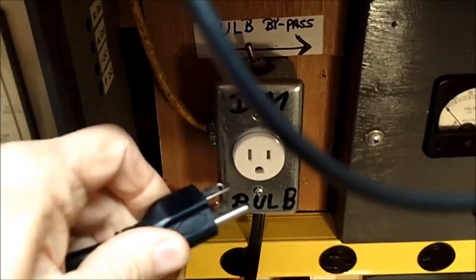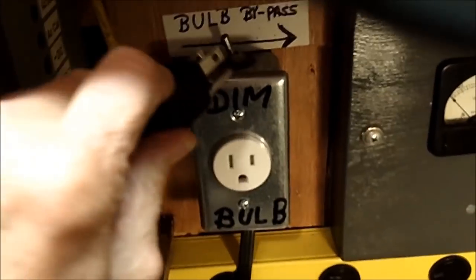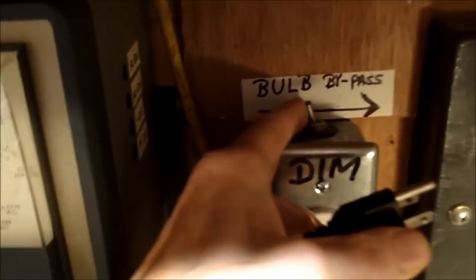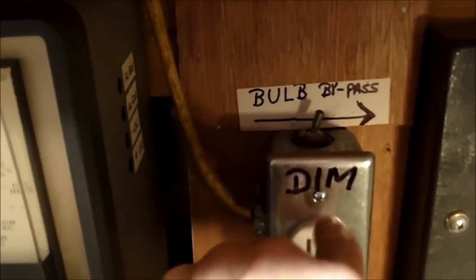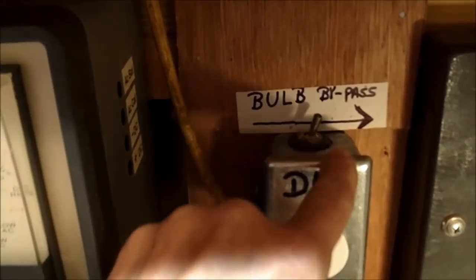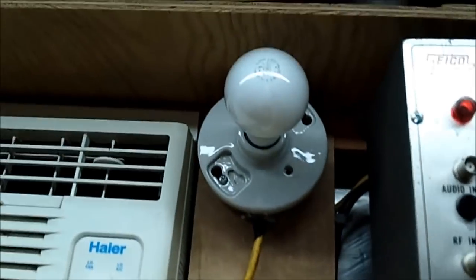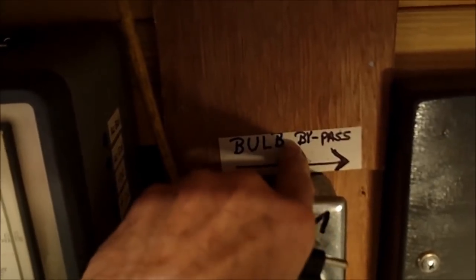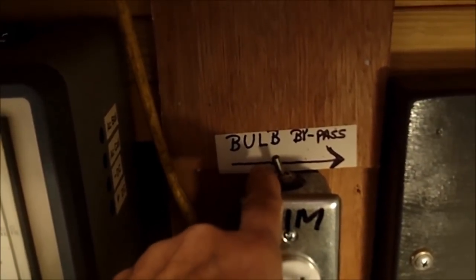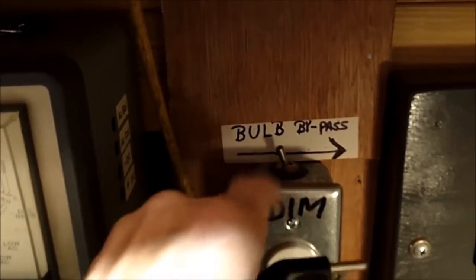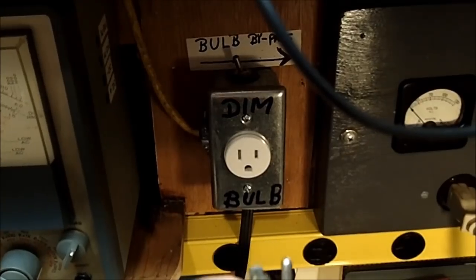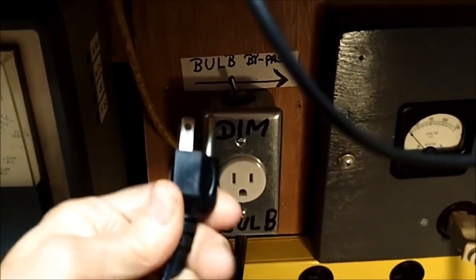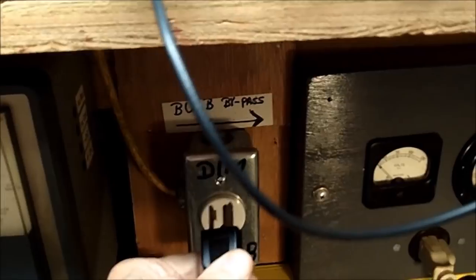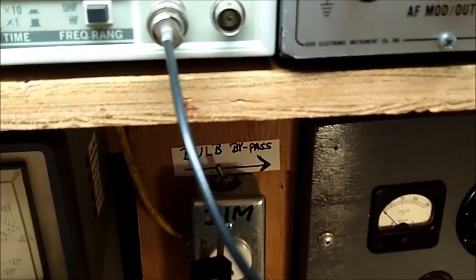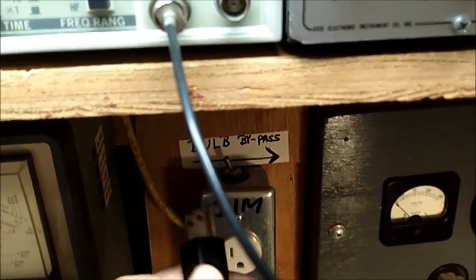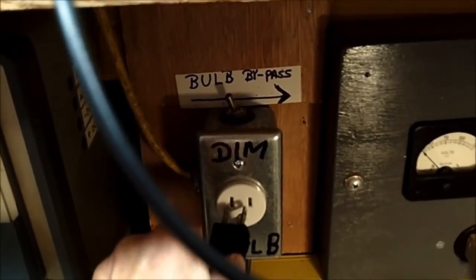Now you're going to be the first, just like myself, to see. Now the way I have my dim bulb here, I have a bypass which shorts out the bulb. But when the bypass is turned off, then we're running through the bulb. So here we go. It'll either go pop, because that DC resistance of that primary is very, very low, and that's got me concerned. Here we go.